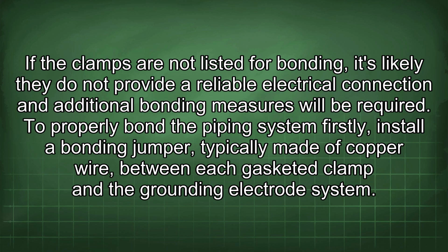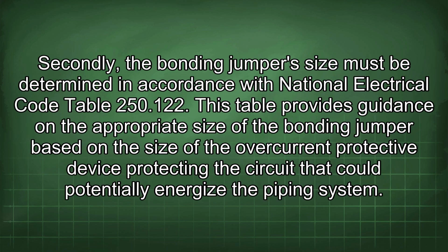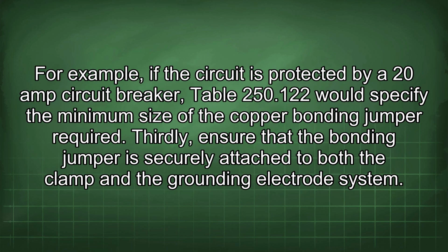To properly bond the piping system, firstly, install a bonding jumper, typically made of copper wire, between each gasketed clamp and the grounding electrode system. Secondly, the bonding jumper size must be determined in accordance with National Electrical Code Table 250.122. This table provides guidance on the appropriate size of the bonding jumper based on the size of the overcurrent protective device protecting the circuit that could potentially energize the piping system. For example, if the circuit is protected by a 20 amp circuit breaker, Table 250.122 would specify the minimum size of the copper bonding jumper required.